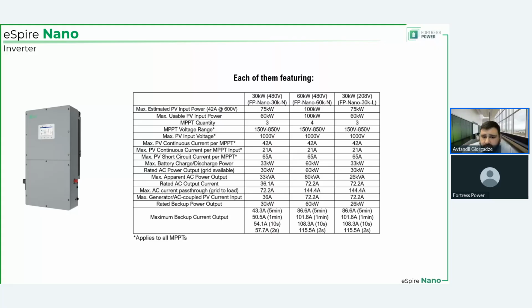But let's be on the point. We are focusing on 480 volt and 208 volts for now. Maybe we're going to have more webinars and more technical overviews for certain geographic areas and the AC signals applicable and commonly used there. So PV input for 30 kilowatt inverters is identical. So on the DC side, when it comes to the capabilities of handling the PV, the 30 kilowatt inverters are identical. They both have 3 MPPTs. The 60 kilowatt inverter has 4 MPPTs.